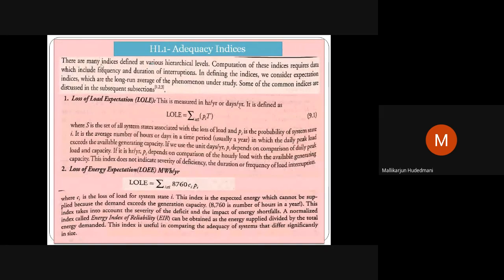Zone 1, this is zone 1. When I measure adequacy of zone 1, what are the parameters I consider to evaluate the adequacy of the system? That is what is here. There are many indices defined at various hierarchical levels. For HL1, loss of load expectation, LOLE, is measured in hours per year or days per year. It means the generation system is unable to serve for a certain number of hours or days in a year. LOLE, loss of load expectation, is the summation over i belonging to S, the set of all system states.